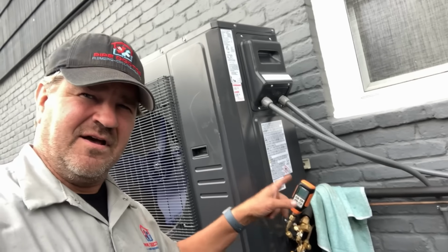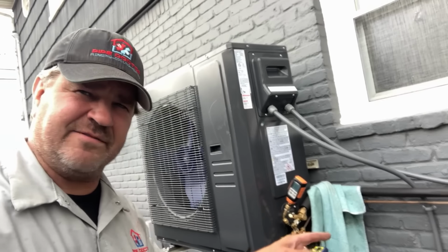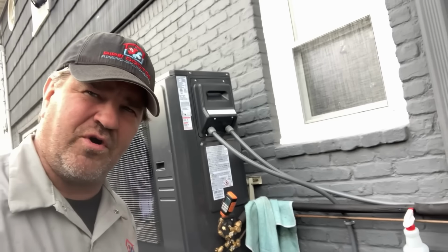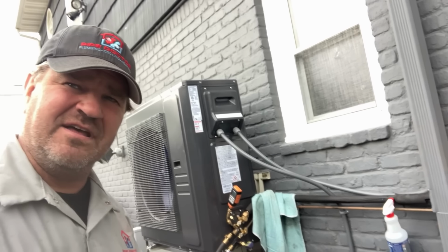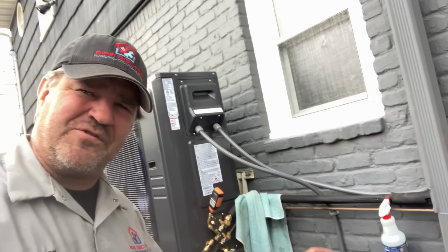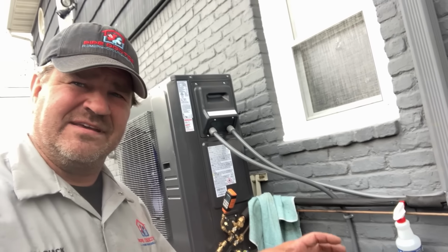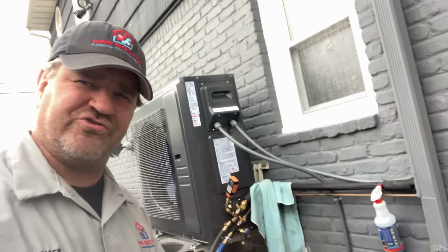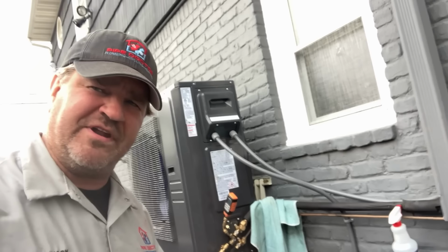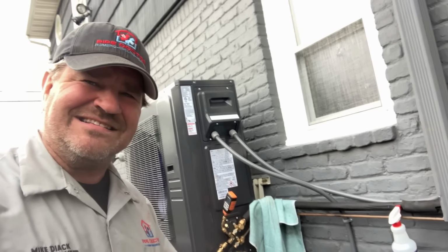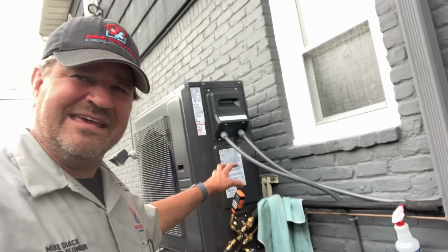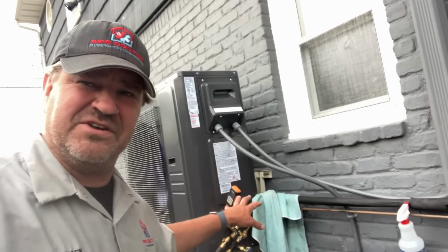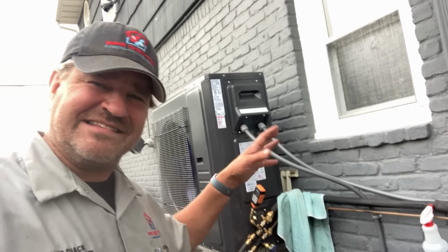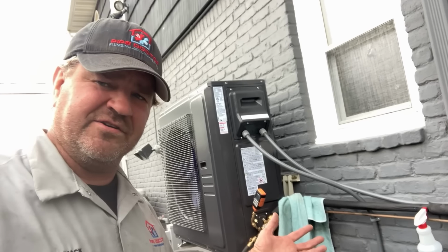Inside of every refrigerant line, every evaporator coil, every condenser, and every line set contains air and moisture. If you don't remove both of them, you're literally sealing contamination inside a hermetically sealed system that's expected to run for the next 15 to 20 years.